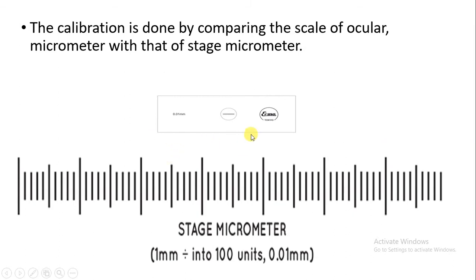The next one is the stage micrometer. You can see it is a slide — it is always kept on the stage. Inside, you can see a line with divisions present — it is called a stage micrometer with an accurate, calibrated scale. The length present on it is in millimeters. The total length you will see is 1 mm, and this 1 mm length is also divided. There are about 100 divisions present. So, 1 upon 100 is equal to 0.01 mm.